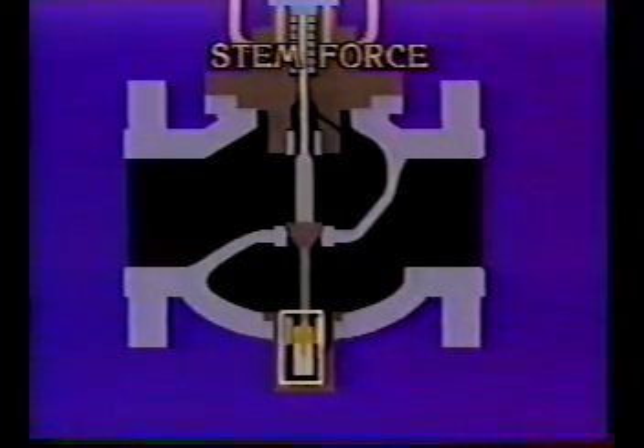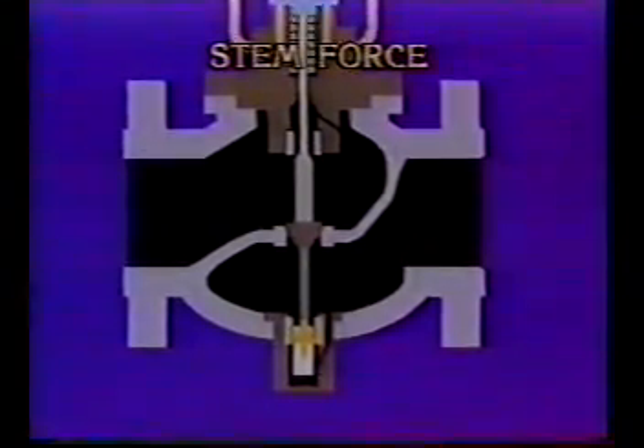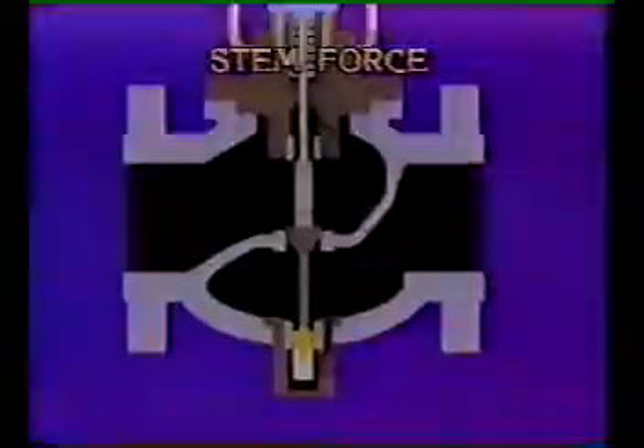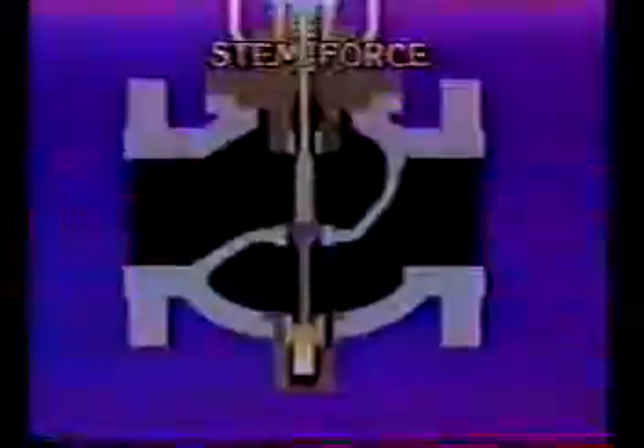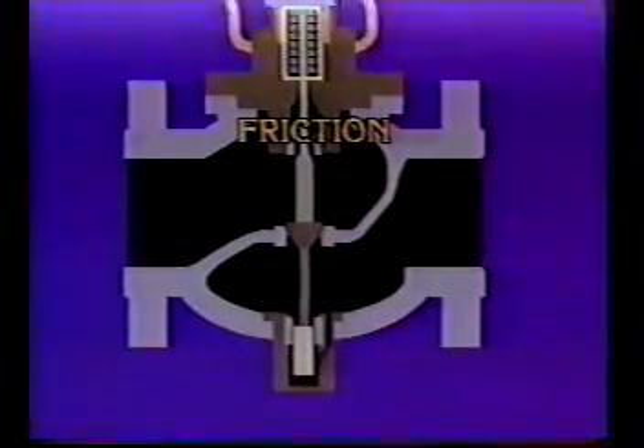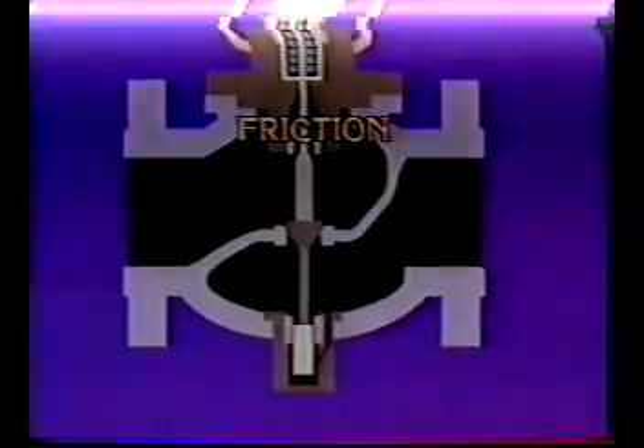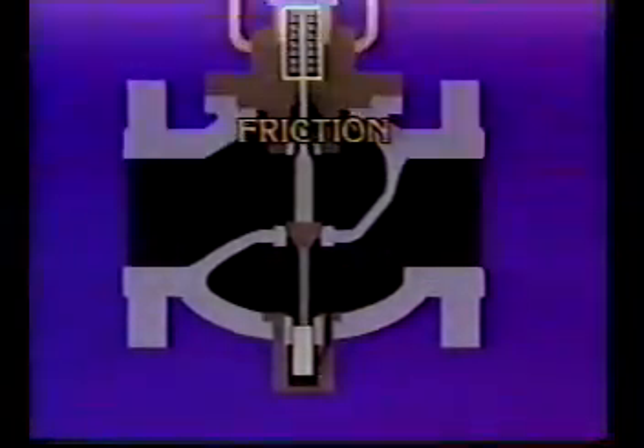Another static force called stem force is developed here at the end of the stem. It's equal to the area of the stem multiplied by the pressure the end is exposed to. This force must be taken into account separately since there is no opposing force in the valve body. Friction is another static force that must be overcome. For linear action valves, stem packing is one of the major contributors to friction. Information regarding the type of packing to be used is critical, since packing friction can vary by as much as a factor of 5, depending on the material that's used.